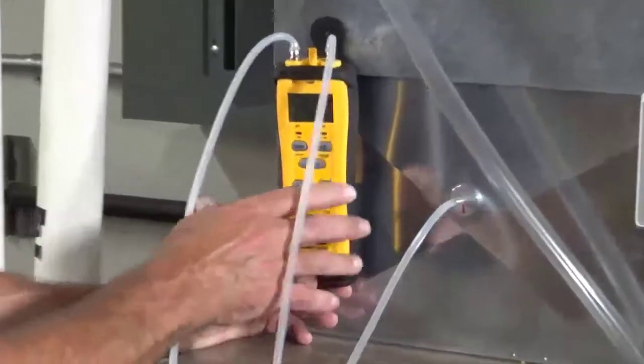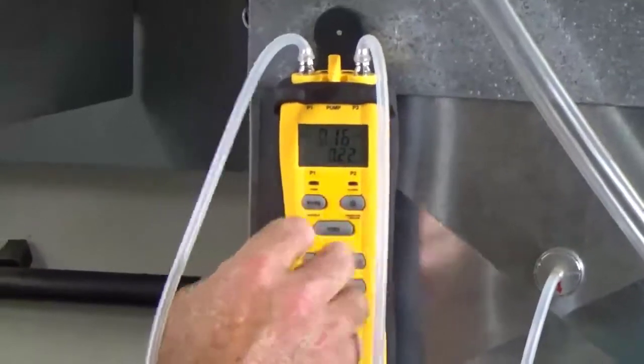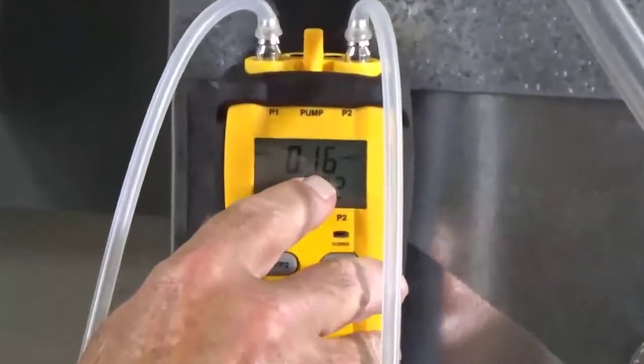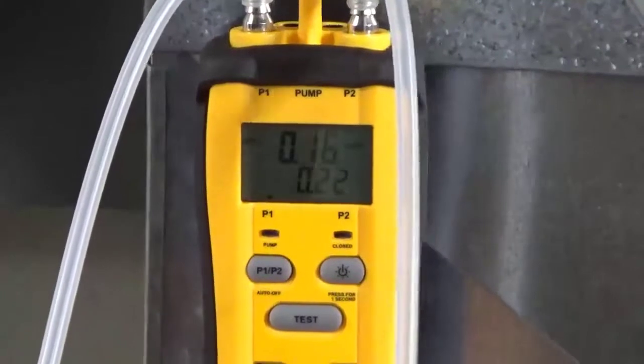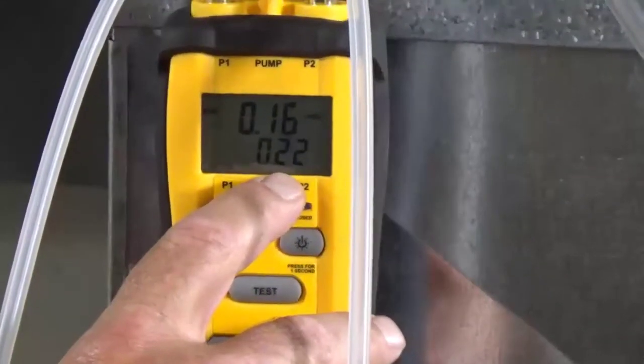So once the blower starts this is showing two different numbers. The P1 which is this tube here is showing our supply side is at 0.16 inches water column of static. The bottom number is our total external static at 0.22.